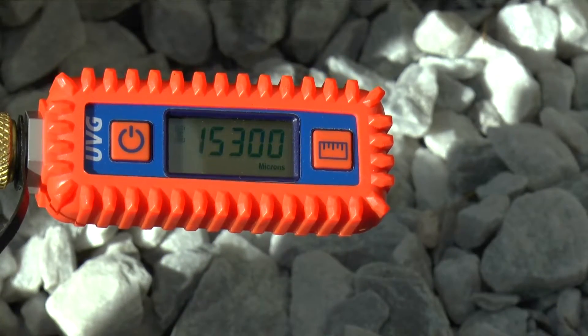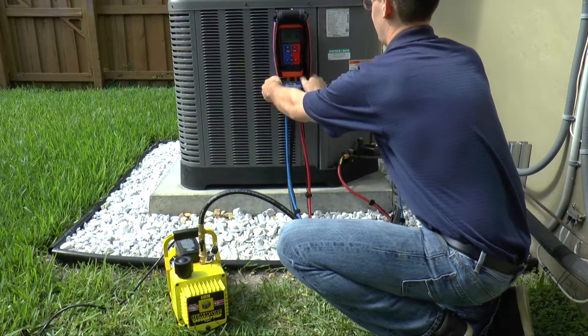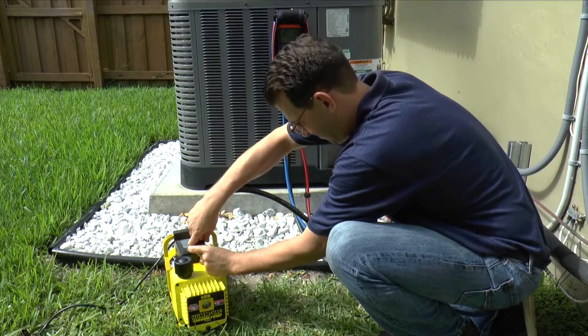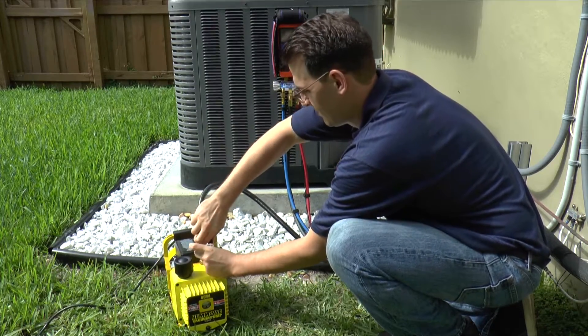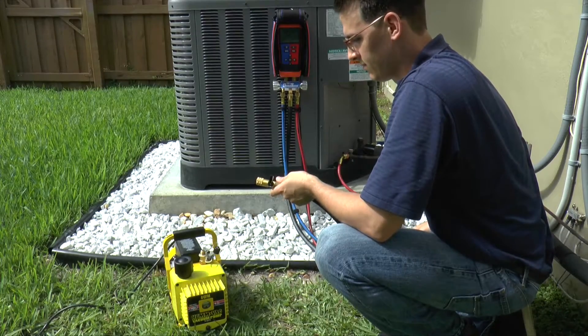Evacuate the system according to the manufacturer's specification. Then close the low side and high side manifold valves, close the ball valve on the black 3/8 inch hose and disconnect from the vacuum pump. Turn the vacuum pump off and proceed with charging the system with refrigerant.